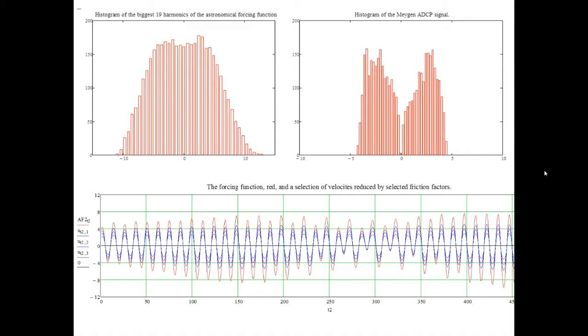I need to have a concept of what I call the flow impedance. This is the determination of the water to get through a passage, and you can define it as the increase in head divided by the reduction in the flow rate. We really need to understand that just as much as we need to know what the density of water is to design these things.